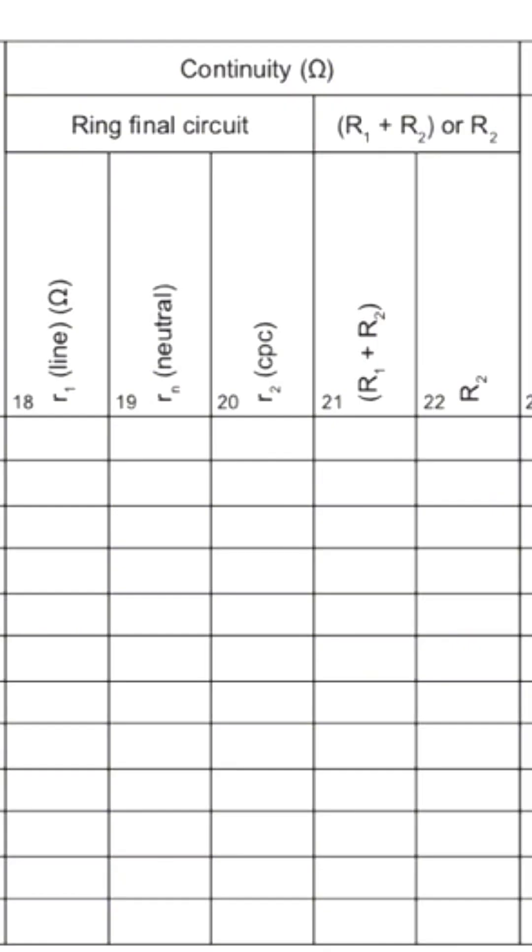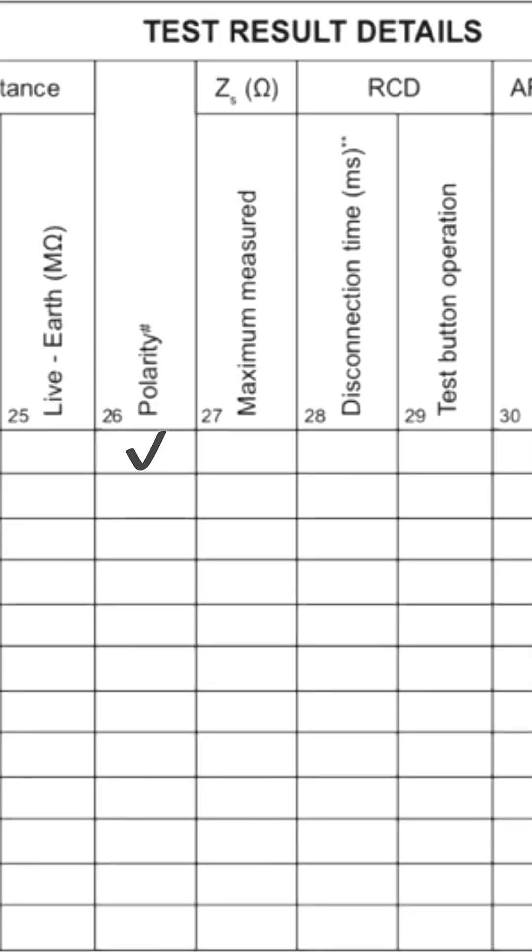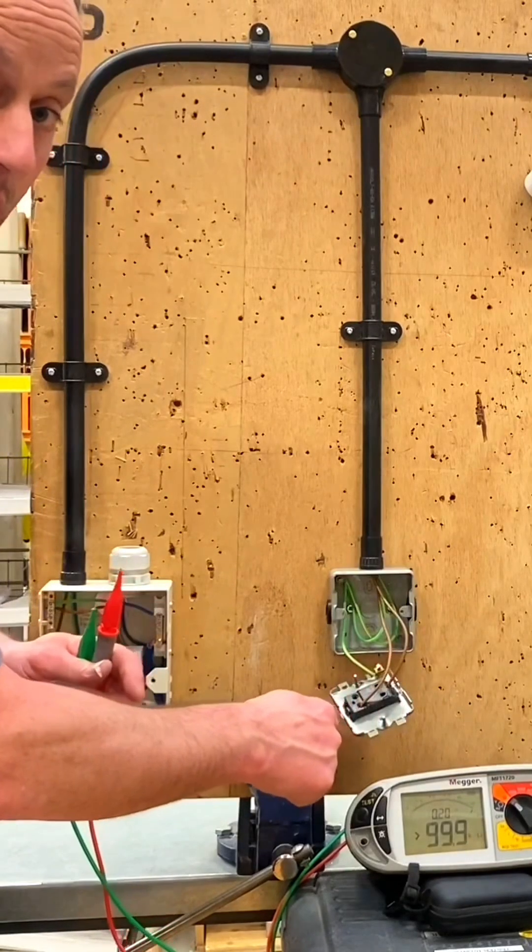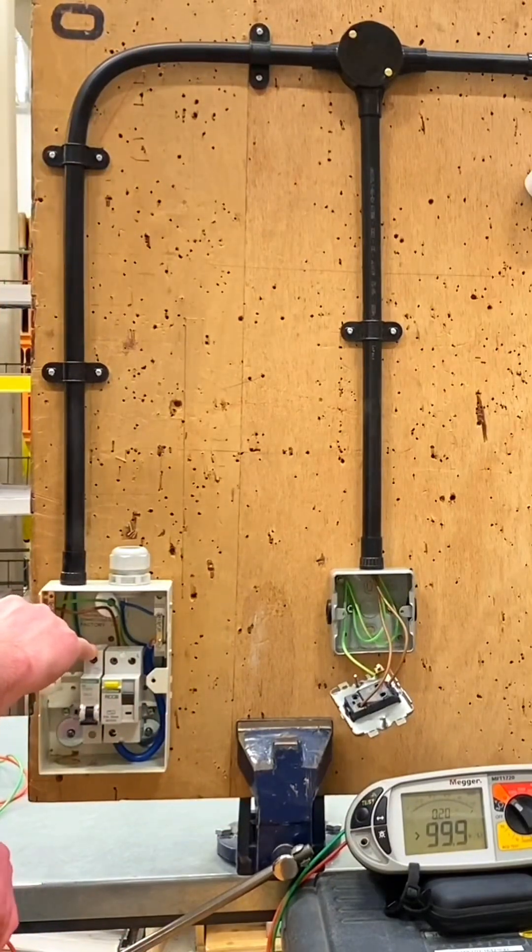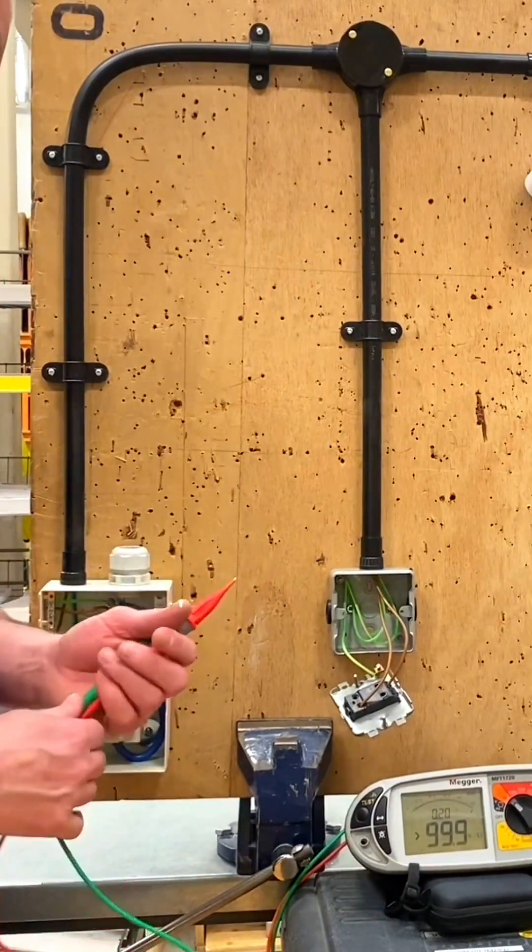Of all the readings we get, we record the highest one in the box heading R1 plus R2 under the continuity test. We can then tick the polarity box, proving that we switch and fuse in the line conductor. The switch was connected in the line conductor and we've got this brown conductor that would be in the fuse as part of our polarity test.